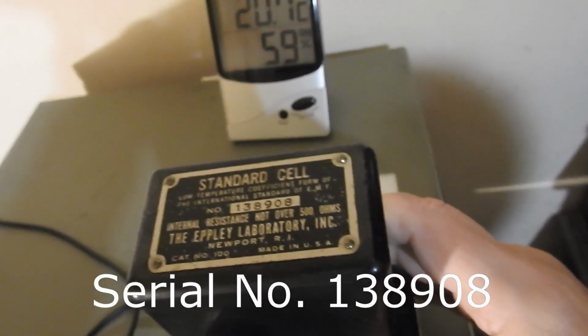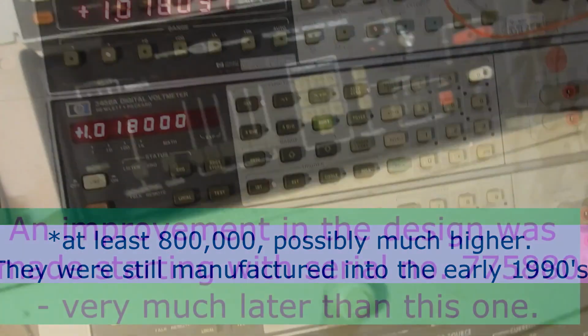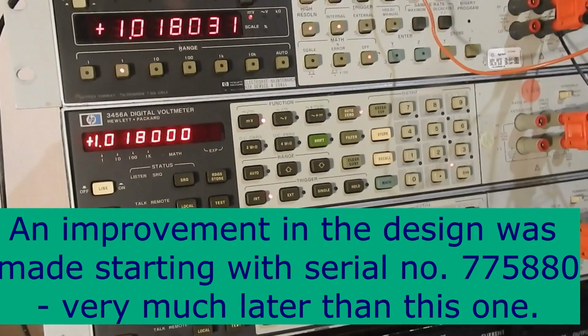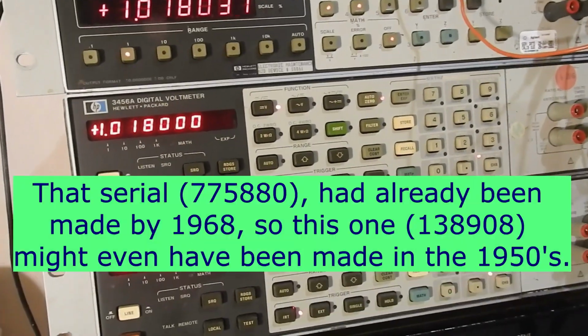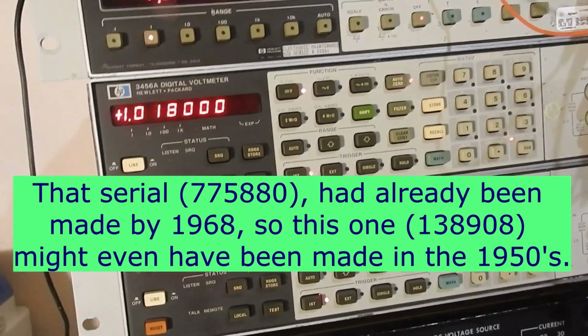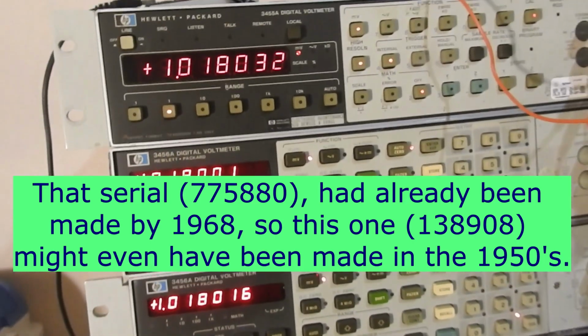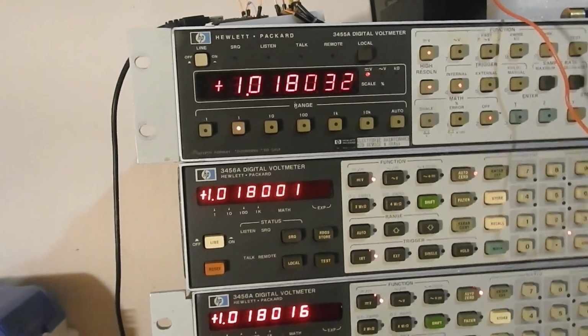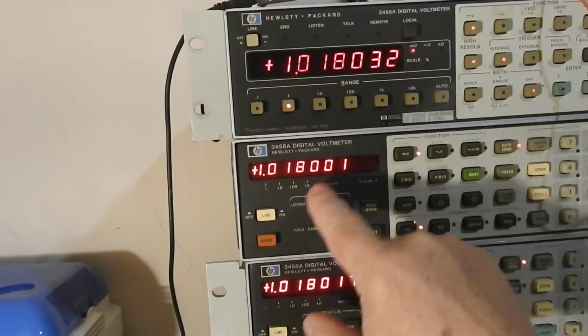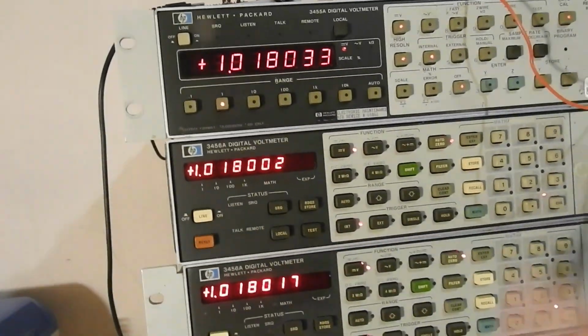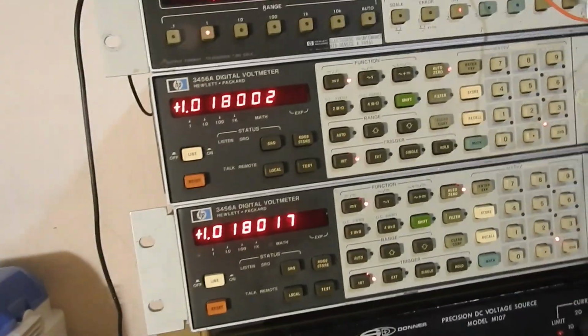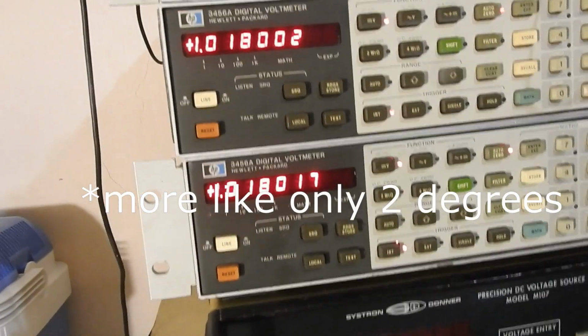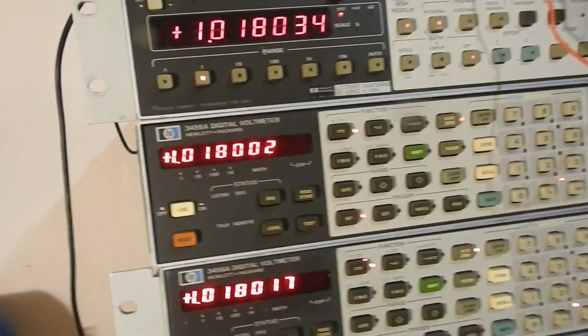As you can see, the serial number on this is 100 and something thousand, and they were made up to around about 800,000. So this is a very early one. It was probably made in about the 1960s, and they're only good for 5 or 10 years apparently, so this is well past its use by date. Even though it's still producing 1.018 volts, the last three digits wobble around quite a bit with temperature, and the temperature's only moving 3 or 4 degrees Celsius, so it's quite sensitive to temperature.